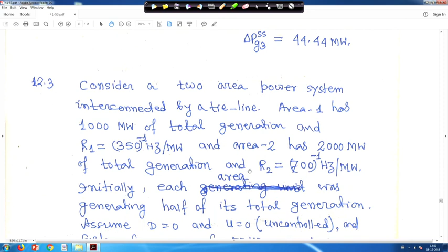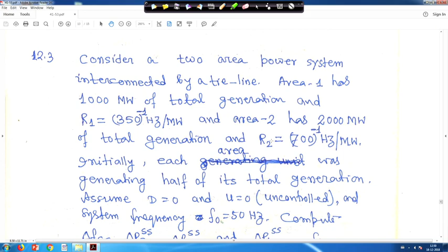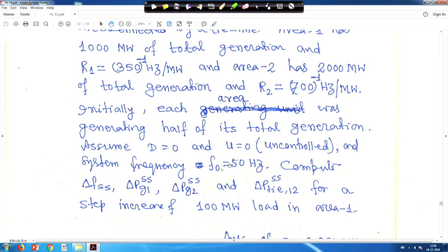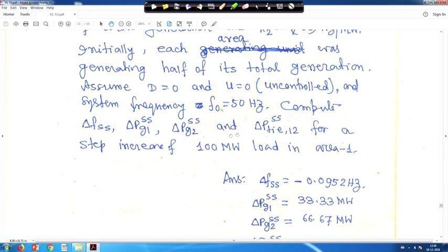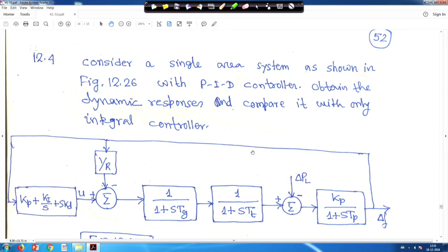Consider a 2 area power system interconnected by a tie line. Area 1 has 1000 megawatt of total generation and R1 is equal to 1 upon 350 hertz per megawatt, and area 2 has 2000 megawatt of total generation, R2 is equal to 1 upon 700 hertz per megawatt. Initially each area was generating half of its total generation. Assume D is equal to 0 and U is equal to 0, where U equal to 0 means uncontrolled, and system frequency F0 is 50 hertz. Compute the steady state values of frequency, generations and tie power for a step increase of 100 megawatt load in area 1. These are the answers.